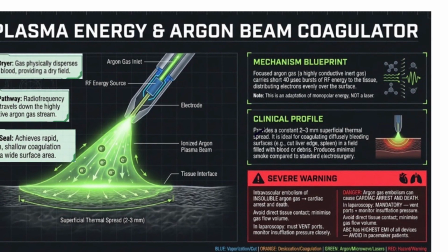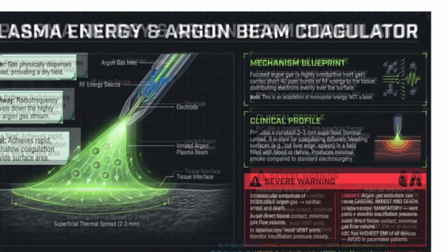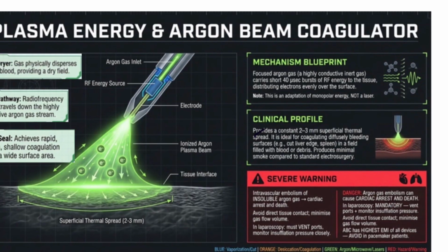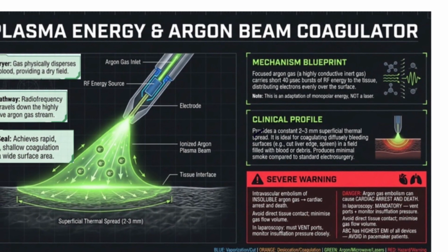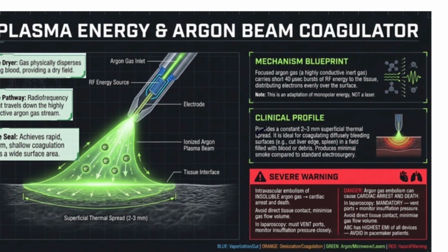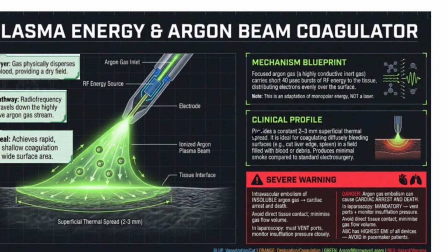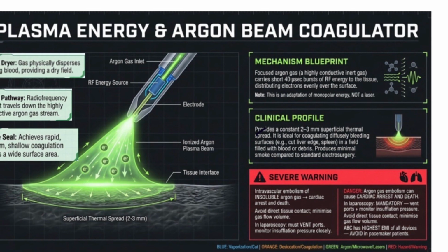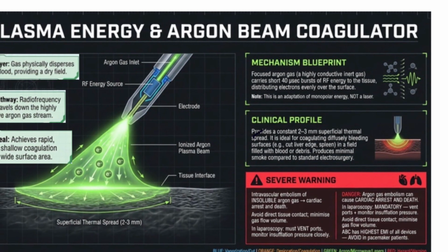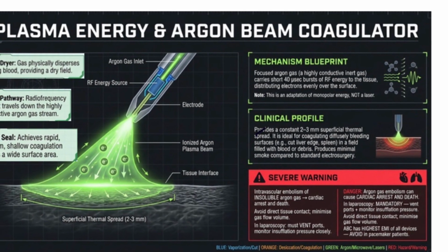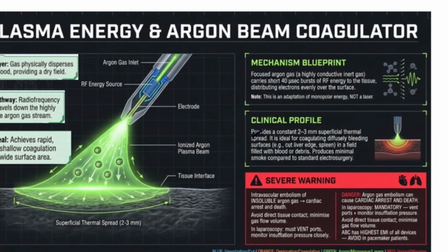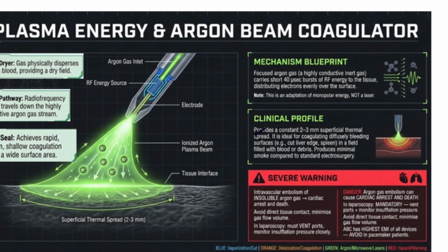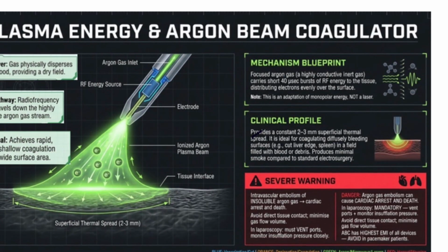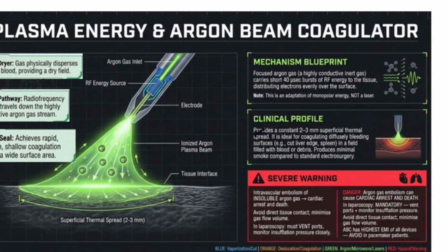This is an adaptation for monopolar energy and not a laser. It provides a constant 2 to 3 mm superficial thermal spread. It is ideal for coagulating diffusely bleeding surfaces, for example the cut liver edge or spleen, in a field filled with blood or debris. It produces minimal smoke compared to standard electrosurgery. The severe warning is that intravascular embolism of insoluble argon gas can lead to cardiac arrest and death.